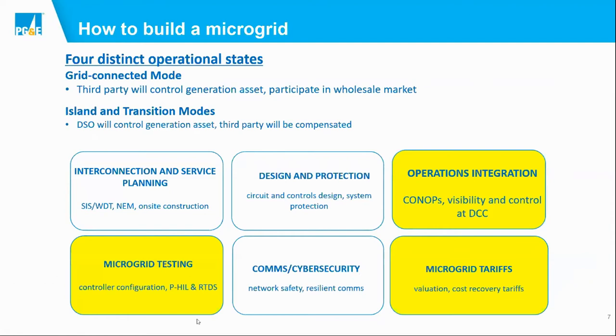That's what we're trying to figure out here. I'm still in learning mode, even 2 years into this project. So I like to think about microgrids in 4 distinct modes. Grid connected mode, where it's basically just DERs connected to the system—you don't actually know it's a microgrid, you don't know it has the ability to island. Then, in the event of some outage or other need to island, the microgrid disconnects from the broader grid and energizes the distribution system. But those aren't the only two modes to consider—you also have to consider the transitions between them. That's actually where a lot of the electrical protection and safety challenges occur.